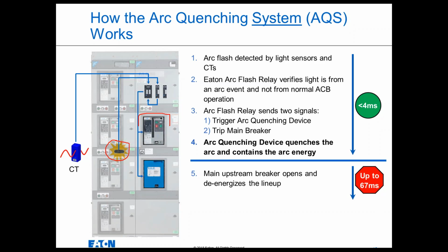And the second one, which is sent out simultaneously, is sent to that upstream overcurrent protective device, that upstream main breaker, telling it to trip. Now, it takes less than 4 milliseconds between when the arc is detected and when the arc quenching device operates and commutates and contains all that arc energy. Then 3 to 4 cycles later, that upstream breaker trips and de-energizes the lineup.